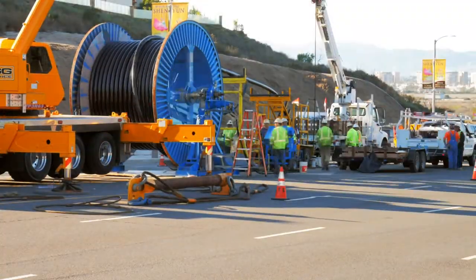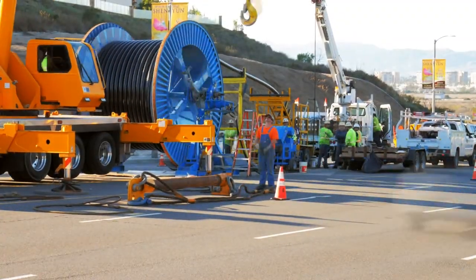However, putting high voltage lines below the ground created a whole new set of challenges. When strung across towers, the conductors at this voltage each require around 10 feet or 3 meters of clearance to avoid arcs. The air is the insulator doing the job of keeping electricity constrained within the conductors. So how do you take those three high voltage phases and cram them into a single small pipe running underground?